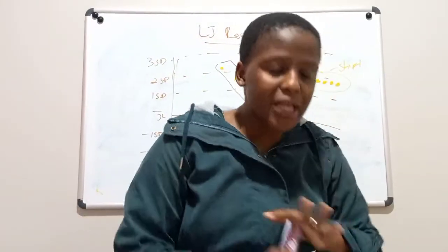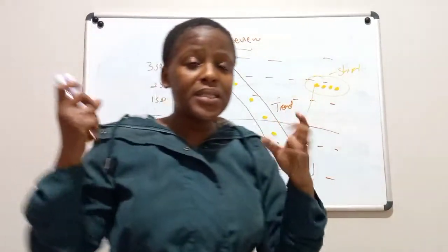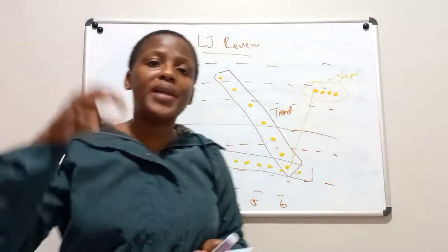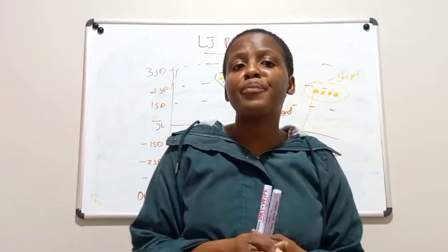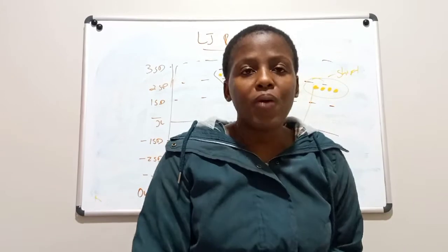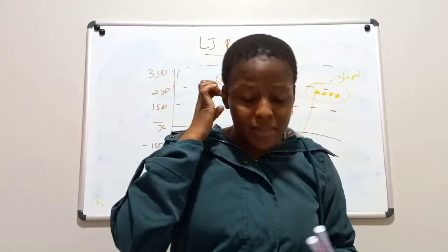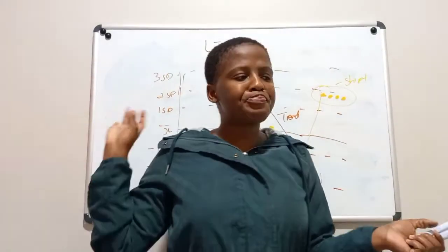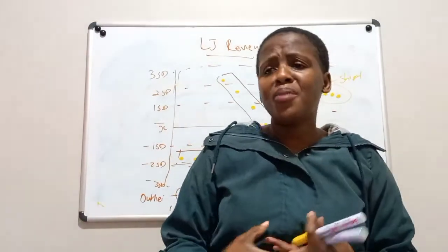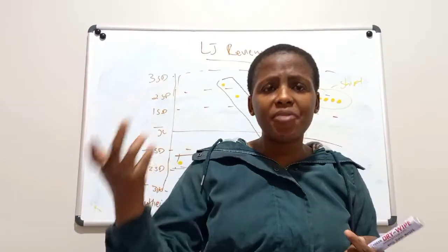With this bias, usually what they will do is, as soon as you see it, you're going to check whether it falls within 1SD or outside the 1SD. If it's within the 1SD, you do not have to troubleshoot it because there is no clinical significance. But once it's outside the 1SD, then it becomes a problem. It becomes a rejection, whereby you need to try to do something about it. And what can cause a bias? A bias can be caused by probably a changed reagent lot, calibration status, the calibrator lot, or the integrity of the calibrator.